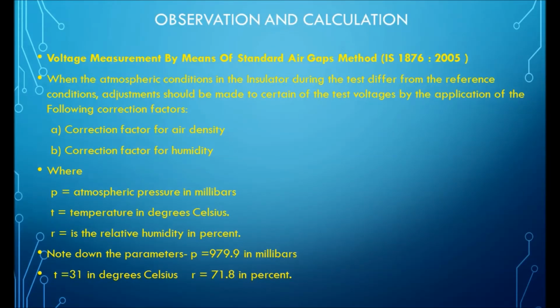Observation and calculation. Voltage measurement by means of the standard air gap method. Follow the IS standard 1876:2005. First calculate the correction factor for air density and the correction factor for humidity. I have calculated these two. First find out today's temperature, pressure and humidity. Today's pressure is 979.9 millibar, temperature is 31 degrees Celsius, and relative humidity is 71.8%.